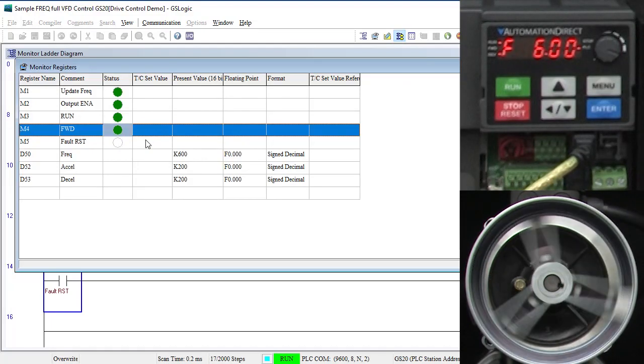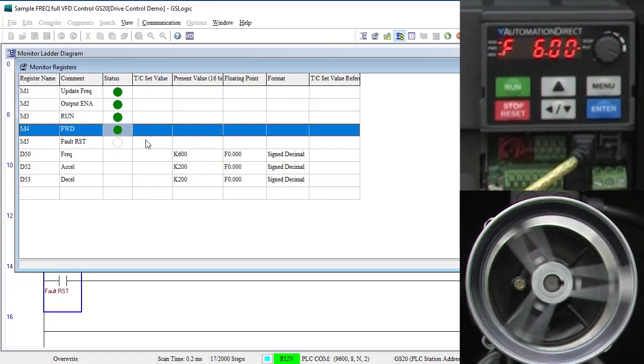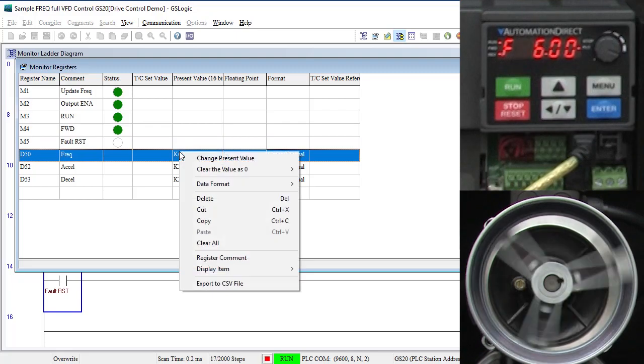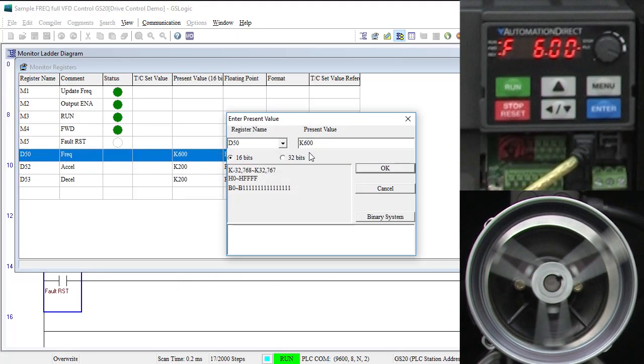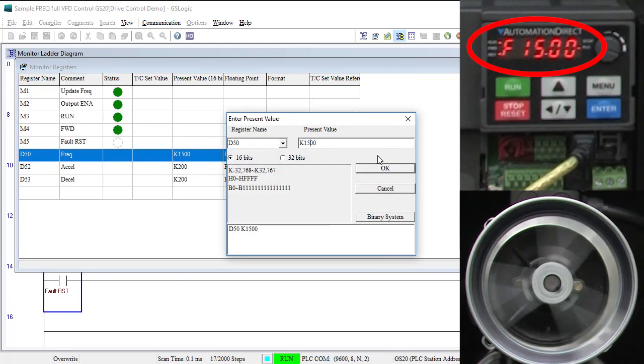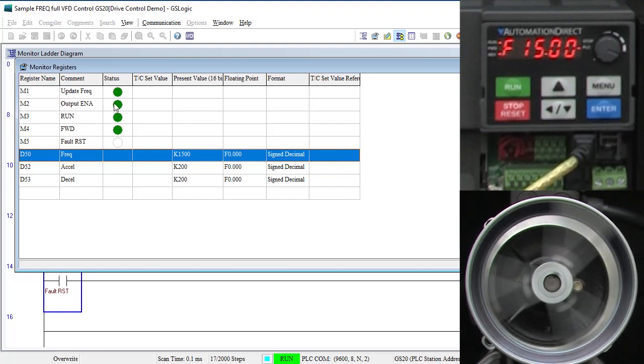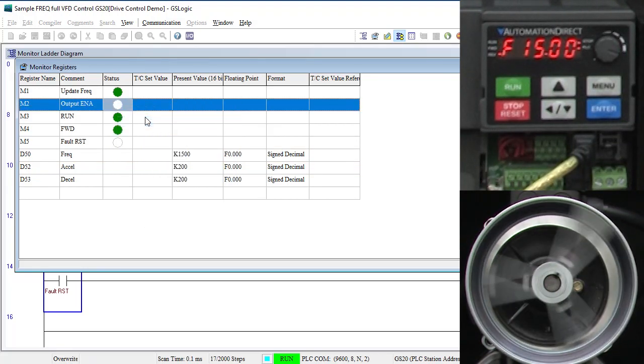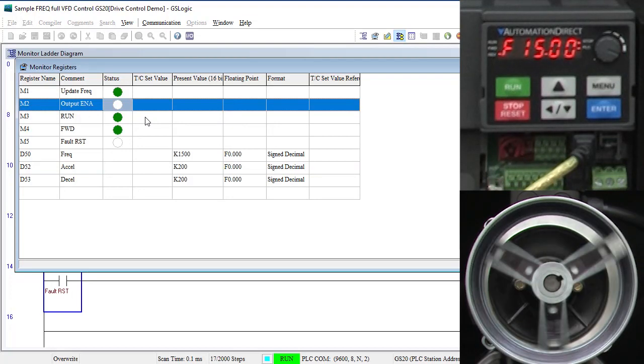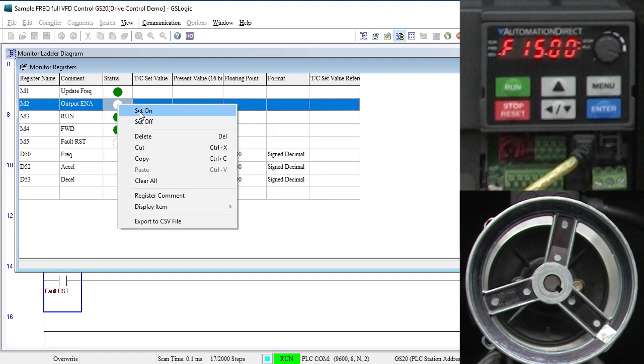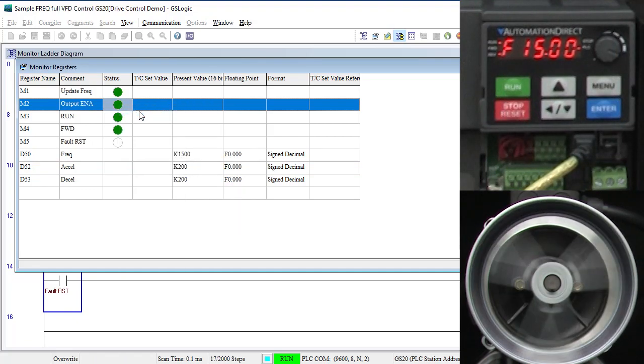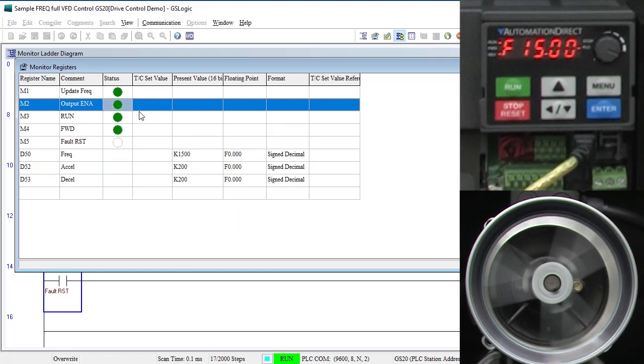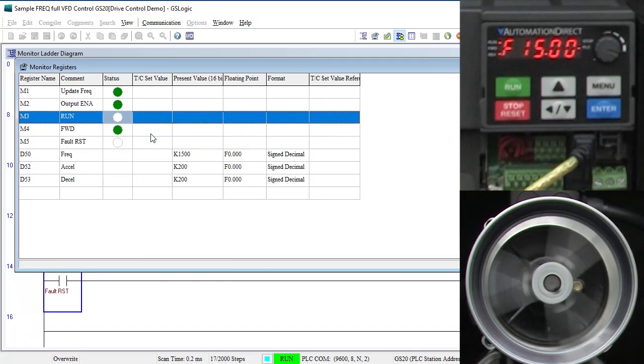Change the forward and reverse bit and the motor ramps down, changes direction and ramps back up. Because M1 is still enabled, if I right click D50 and change the frequency, it changes immediately. If I disable the drive's output, we see the actual output frequency immediately goes to zero with no ramp and the motor free spins to a stop even though the drive is technically still running. Re-enable the output and the drive ramps back up to speed. Turn this guy off to stop the drive with a controlled ramp.